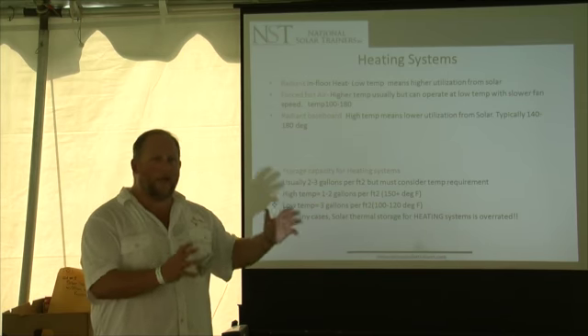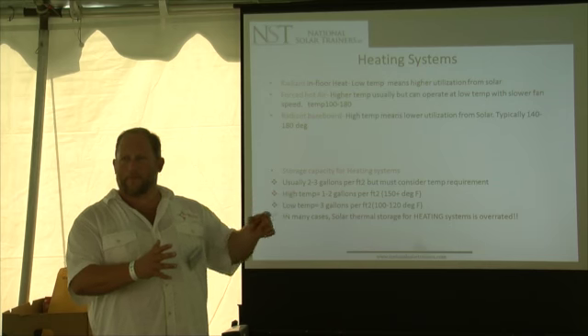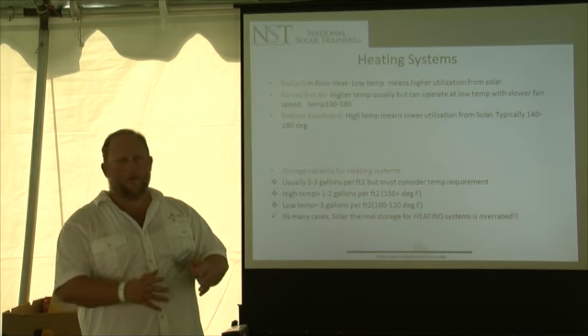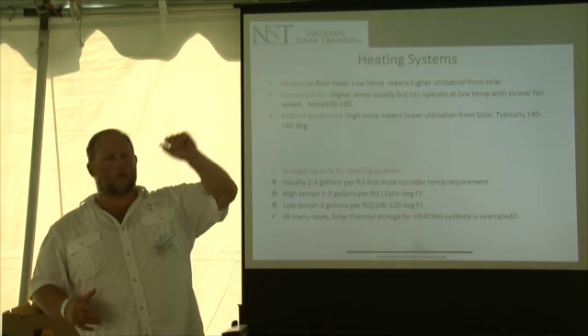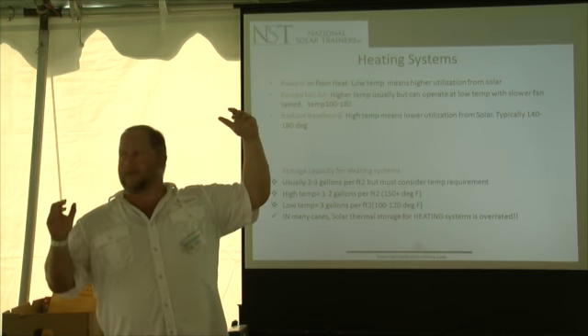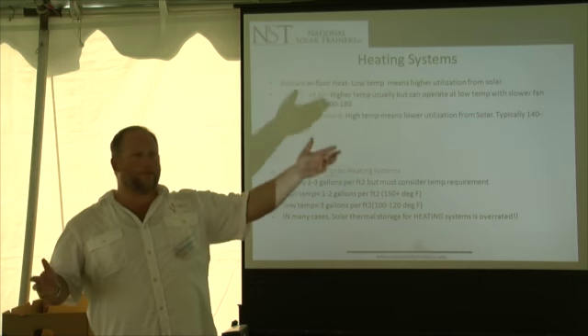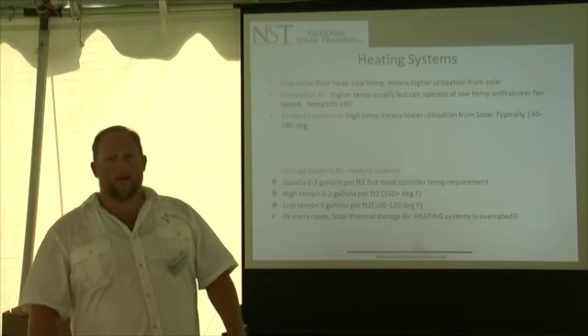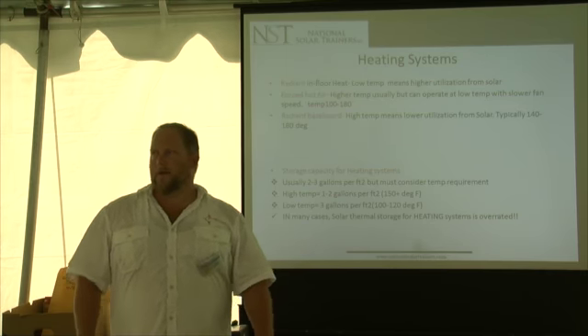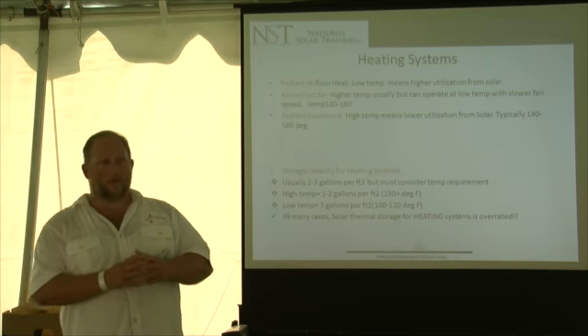You can take all the heat out of that solar loop—you're coming down at 120, going back up at 95. So all day long that collector is running at 95 degrees, which is a perfect efficiency number. So forced hot air is a good candidate for solar hot water.